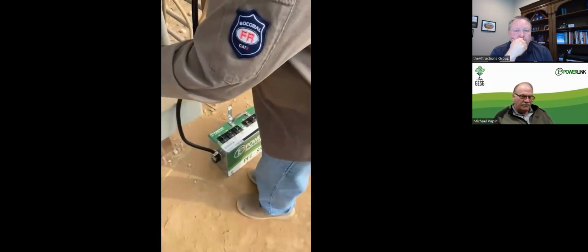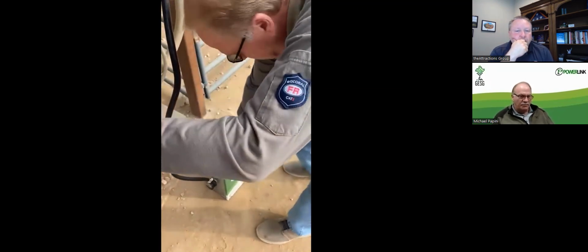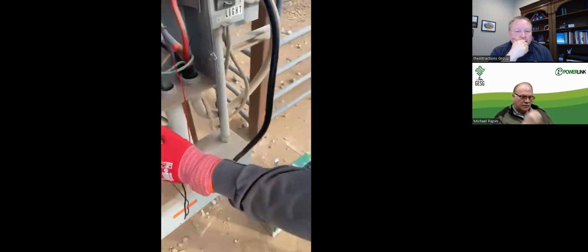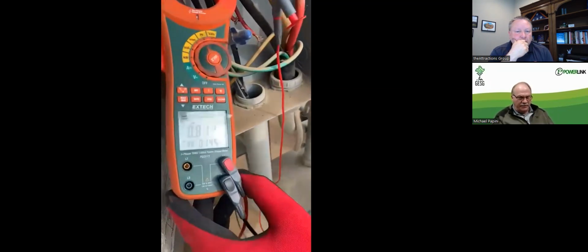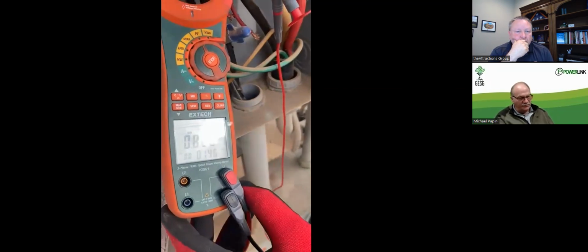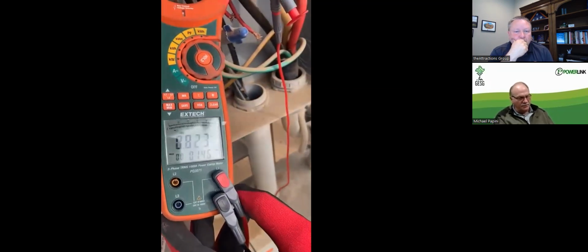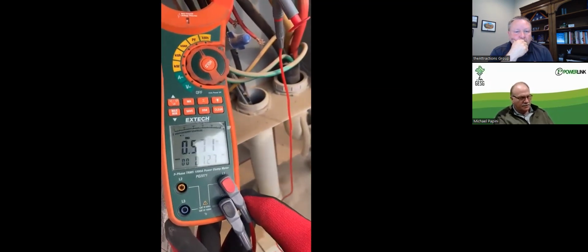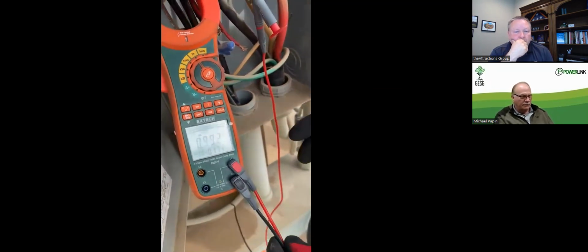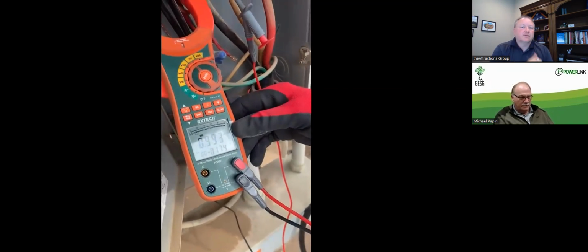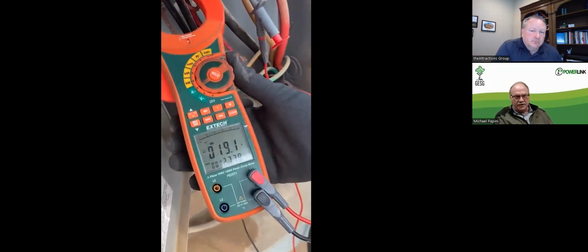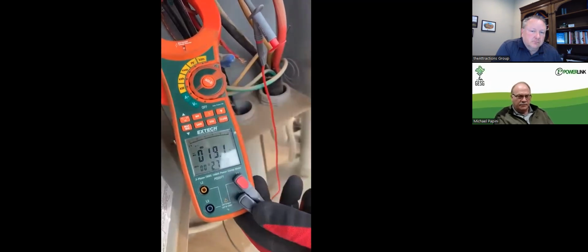So that's what we're doing now, I'm switching those switches on and off, bringing that power factor to a 0.99 from a 0.58. This will give you the instantaneous result. As I switch, you can see the power factor building up, it's 0.82 now, and now it should be 0.99. So when I go back to the amps, it drops down to 19 from 32.